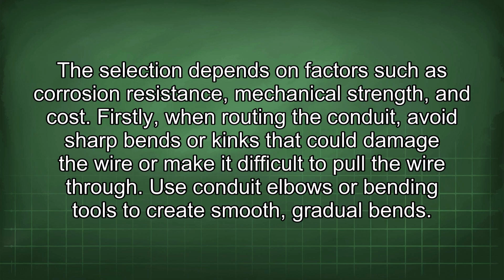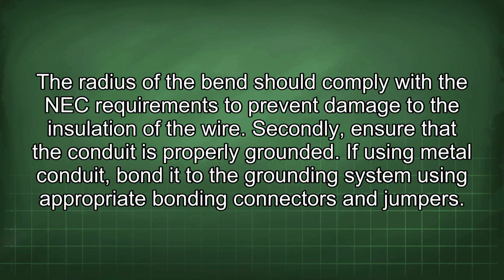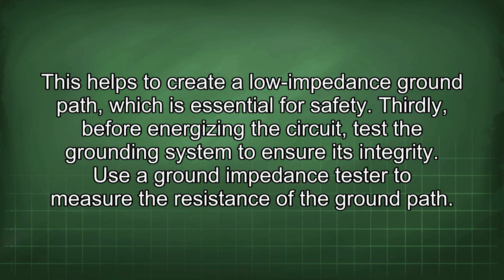Firstly, when routing the conduit, avoid sharp bends or kinks that could damage the wire or make it difficult to pull the wire through. Use conduit elbows or bending tools to create smooth, gradual bends. The radius of the bend should comply with the NEC requirements to prevent damage to the insulation of the wire. Secondly, ensure that the conduit is properly grounded. If using metal conduit, bond it to the grounding system using appropriate bonding connectors and jumpers. This helps to create a low impedance ground path, which is essential for safety.